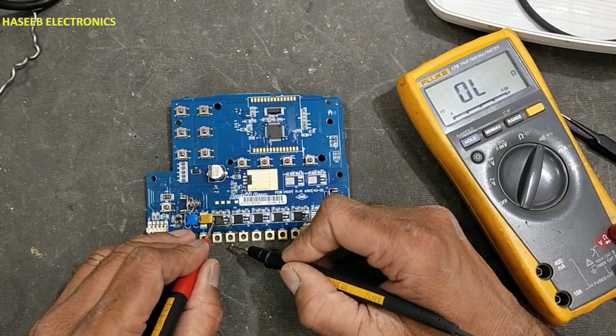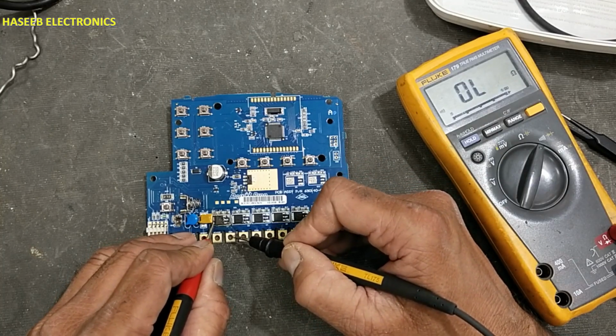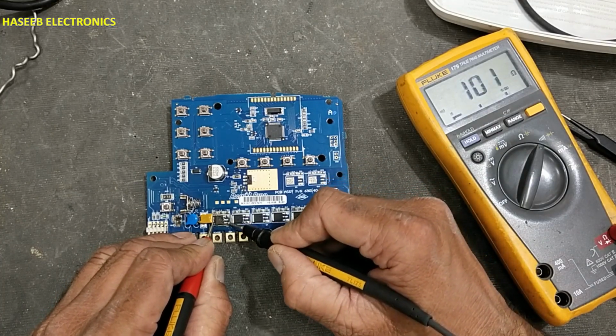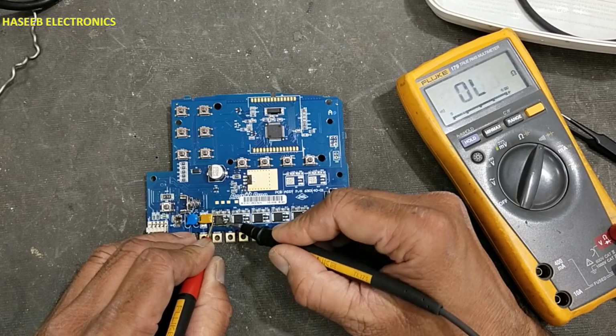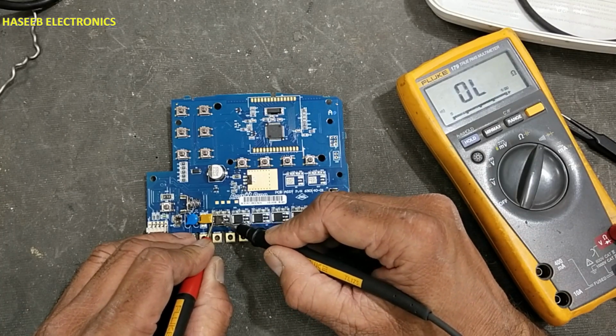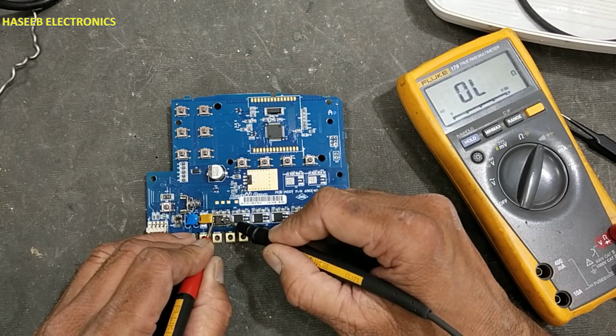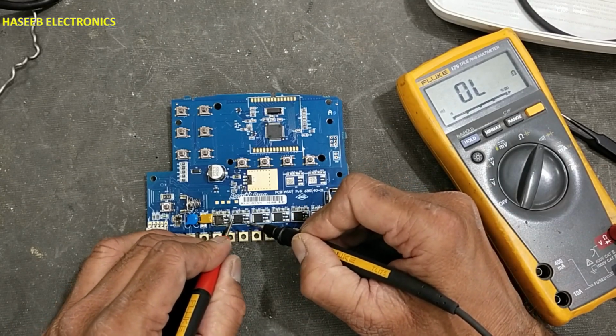If we check resistance between terminal 1 and terminal 2, it is giving resistance. That is not a good sign. This triac is short circuit from terminal 2 to terminal 1. It must be open.